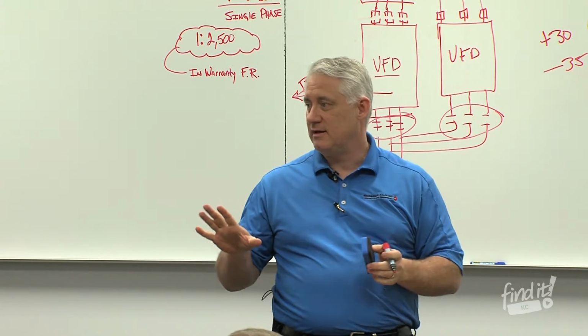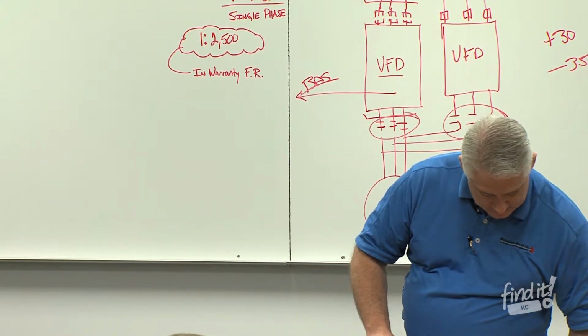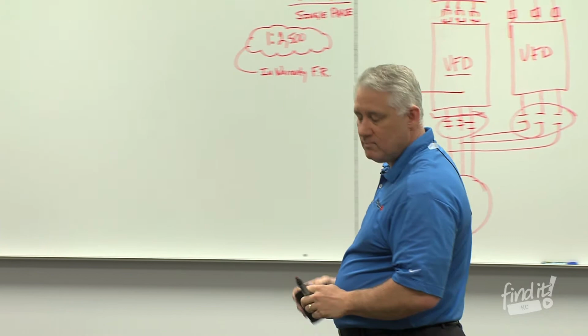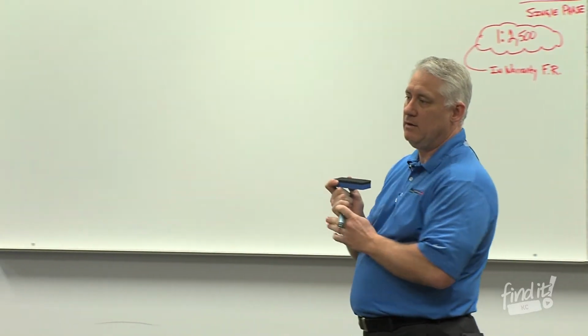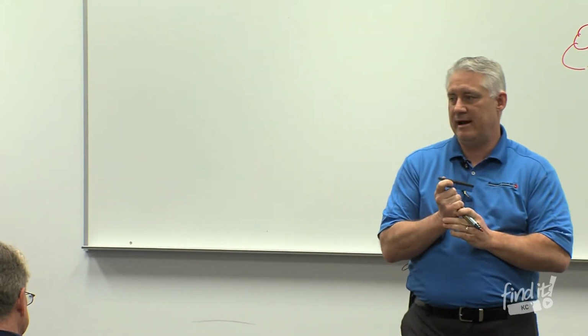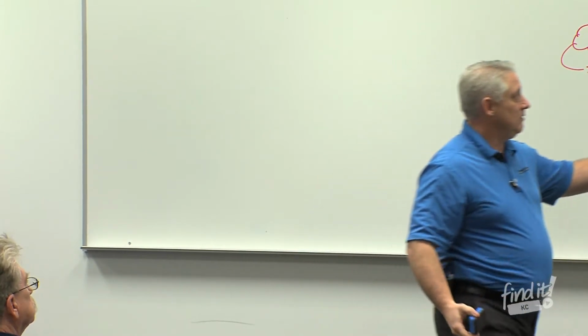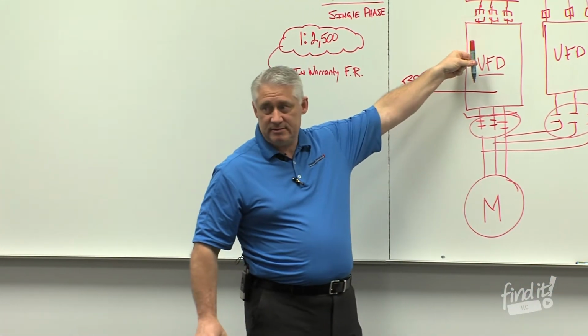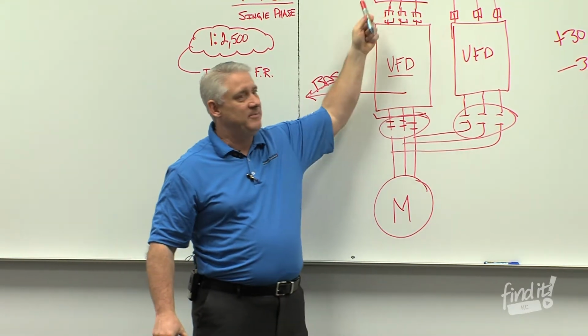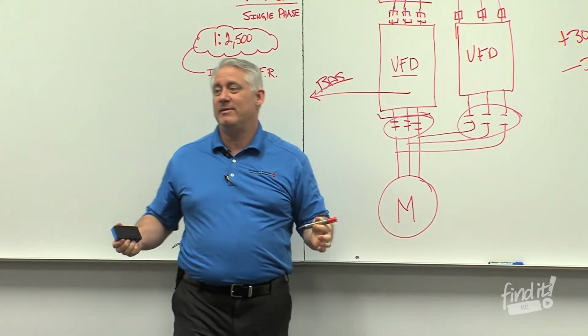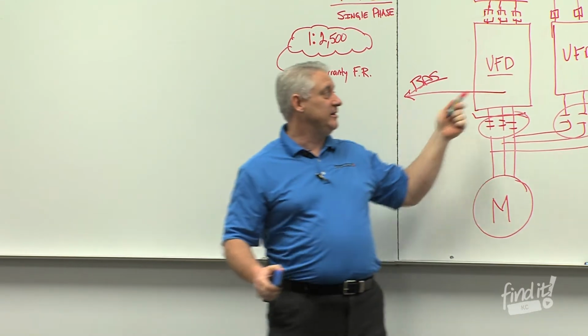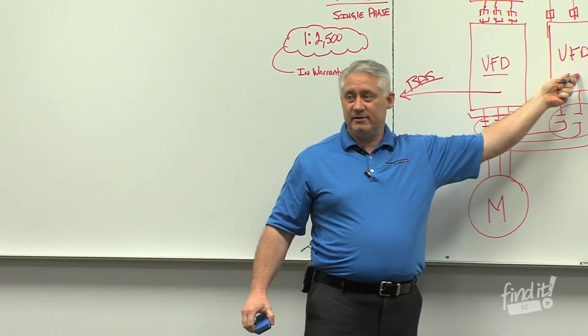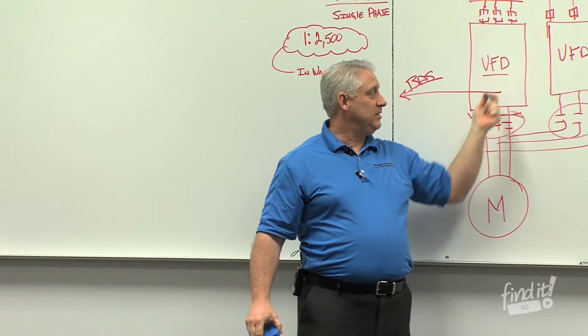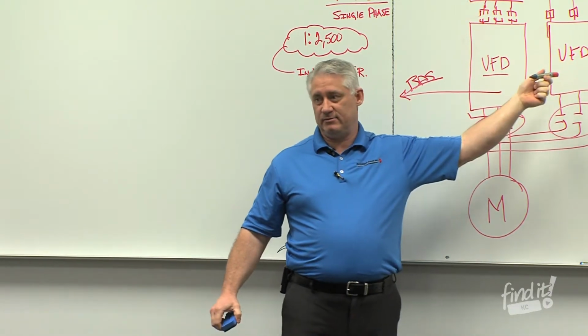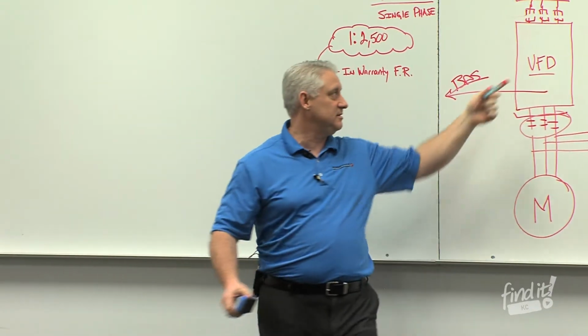So does that make sense? Okay, good. Well, Paul, what's a ballpark 5 horsepower drive with bypass compared to 2 drives? Does that cost twice as much as a drive? Well, what you'll see is the drive is one cost, right? Then we have the adder for the drive and the bypass. And through about 30 horsepower, the drive and the bypass are about the same price. And in a redundant drive package, we're adding another drive. So 1 plus the bypass plus another drive, right? So there's some cost to that. This is one price. This doubles it, and this triples it.